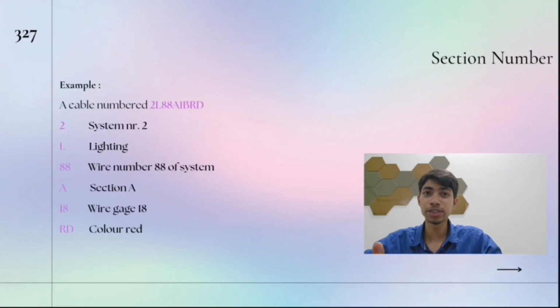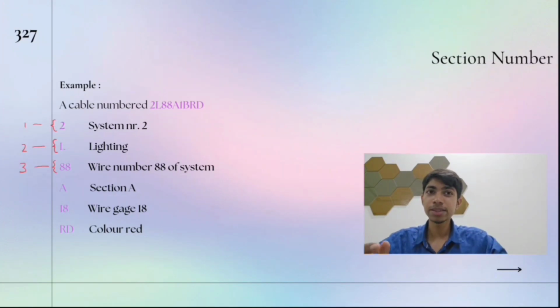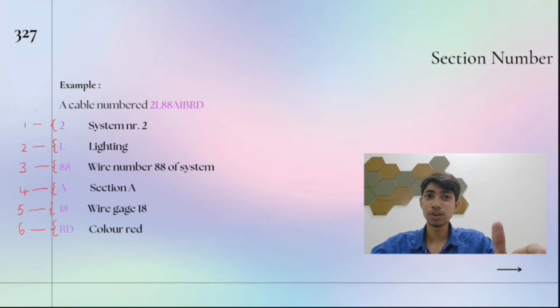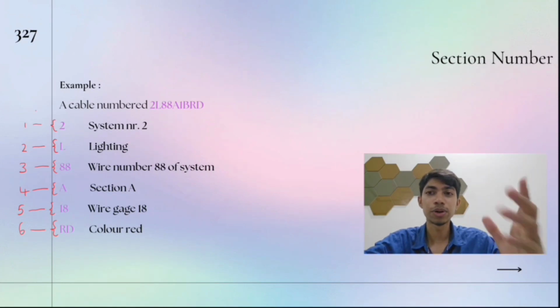This is an example of the coding system where 1 refers to the system number, 2 refers to the system code, 3 wire number, 4 wire section, 5 wire size and 6 is the color phase. As for 2, it is system number 2, L is for lighting, which you can refer to in the letter code, and 88 is wire number 88, A is section A, 18 is the gauge size, RD is for the color red for the wire.